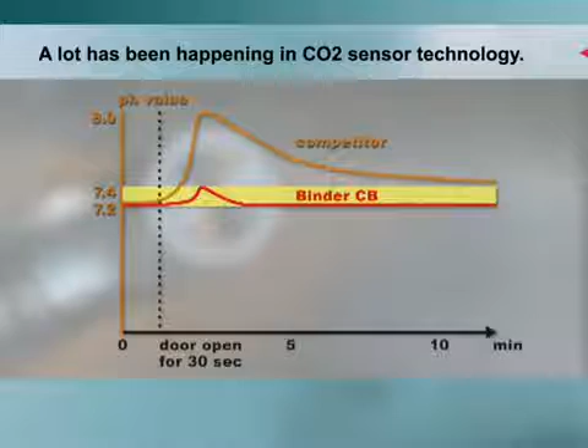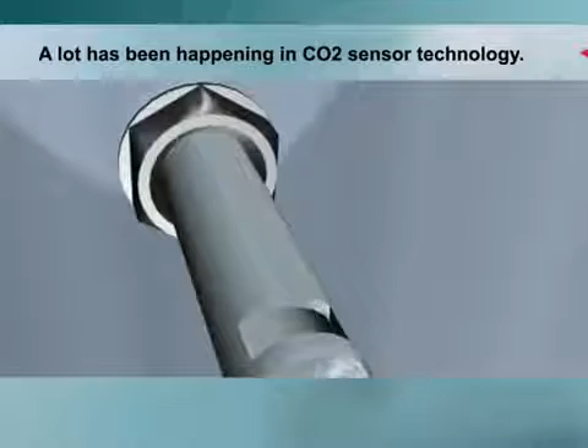As can be verified, this rapid infrared measuring system also provides a reliable readout of the actual CO2 levels in the interior chamber. Fans for the even distribution of the CO2 gas are therefore not needed. This is a special plus for safety. Possible risks such as stirring up of contaminants in air currents or dripping of condensed water are practically ruled out.